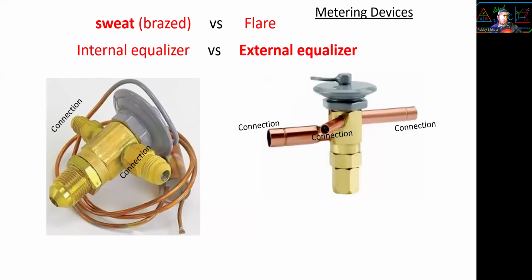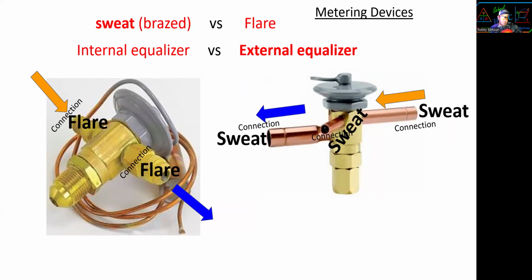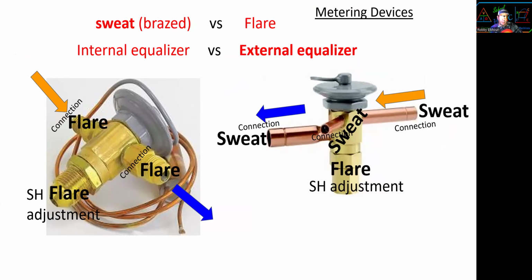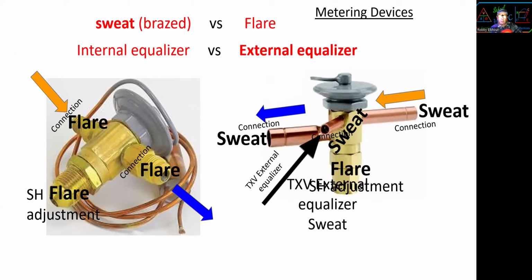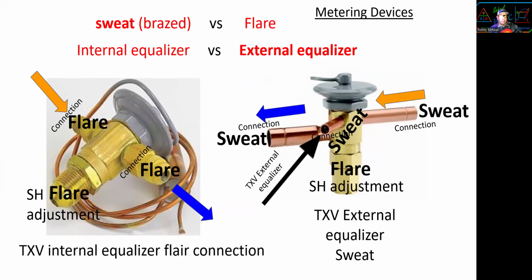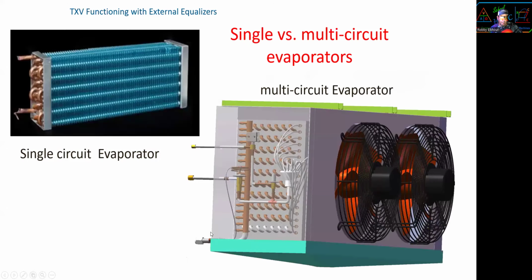All right, now we have sweat, the brazing type, internal equalizer versus flare and external equalizer. Sweat versus flare, internal versus external. So the connections: suction, liquid line, and expansion line. The one on the left has flare nuts, and the other one is sweat, you braze it in. And the adjustment is at the bottom. This one has an external equalizer. We're going to talk about that, very important. So that one is an external equalizer sweat connection, and internal equalizer flare connection.